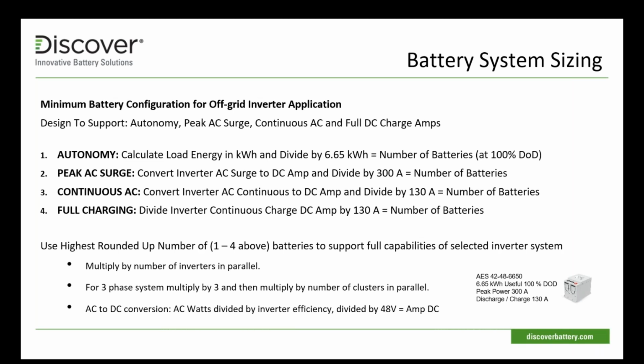However, we also need to consider the peak surge capability, the continuous AC output of an inverter, and its full charging capability. Calculating those numbers as outlined in the 1, 2, 3, 4 steps, doing that simple math, will give you the number of batteries, and out of those 4 calculations you select the highest number of batteries. That delivers a system with batteries that will support the peak capabilities of that inverter, charger, solar charge controller system.